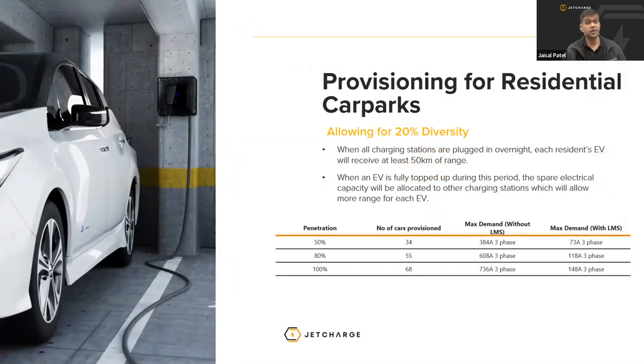So in terms of provisioning for residential car parks, what should we allow for? So we allow for a diversity of 20% for a residential car park. So if you're designing an apartment building, we like to diversify our charging figures down to 20%, which is in line with the draft NCC 2022 standards, which require 12 kilowatt hour available charge for each charging station installed over 8 hours, which is essentially the same as 20% diversity.